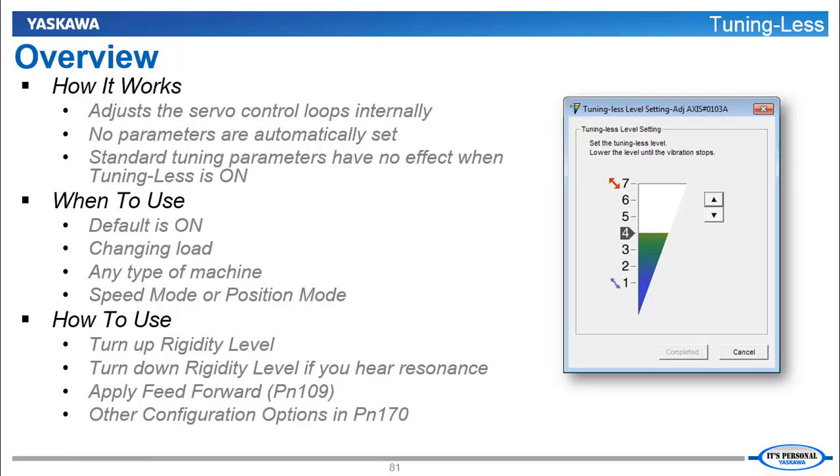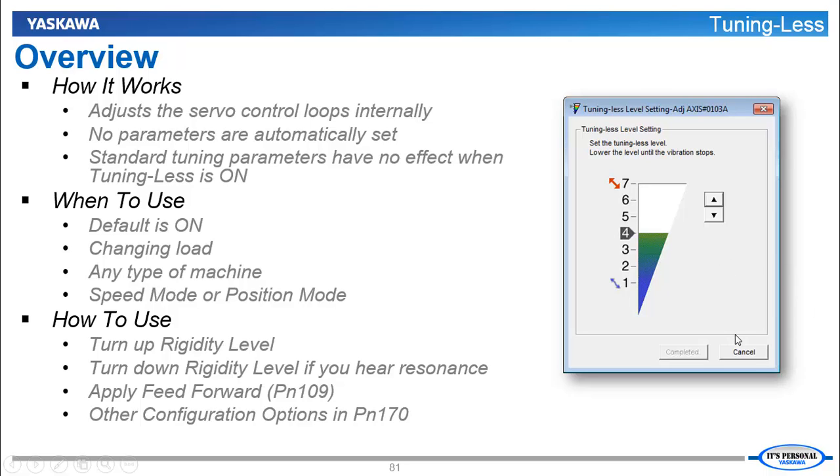Basic Usage. You can try to get better performance by turning up what's called the Level. We'll show you how to get to that here in a minute. If you hear resonance or noise that is not automatically filtered out, you can also just turn down the Rigidity Level and the response still may be acceptable for your application. If you need better response, you can apply a Feed Forward parameter.